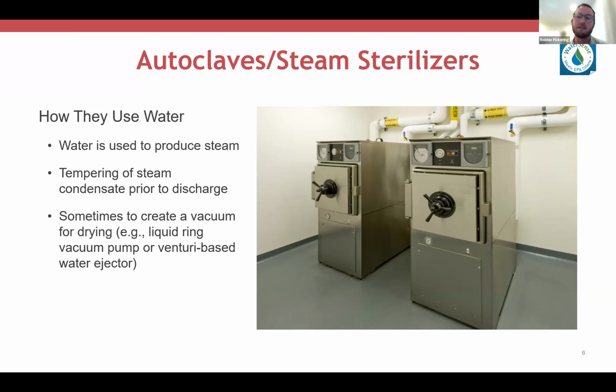In older systems, this can usually be about 1 to 5 gallons per minute, and this is often running continuously even when it's not needed. This is often controlled by a needle valve that, as time goes on, the flow rate tends to creep upward. So even if you think you're using only 1 gallon per minute, or that's what you set it at 5 or 10 years ago, it's possible or even likely that flow rate is now much higher. So it's good to evaluate that periodically. And then lastly, some steam sterilizers use a vacuum system to assist with material drying. Both liquid ring vacuum pumps and Venturi-based water ejectors use water in that process. And so this can sometimes add an additional 5 to 15 gallons per minute of water use to these systems.